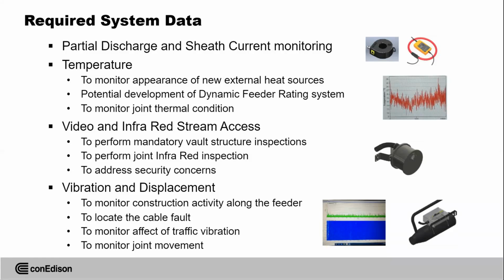So first, of course, we look for partial discharge sensors. I'm sure most of the people on the call know what it means, but just a few seconds to explain. Full discharge is from conductor to the ground. Partial discharge is any incomplete discharge in between. Somewhere in the insulation, in the middle or close to the conductor or close to the shielding, any voids, any imperfection can create a temporary discharge, which may not affect anything if it's alone, but if there are a lot of them and they start happening routinely, they may damage the insulation or reduce insulation strength. And that's what can start happening and eventually will lead to failure.